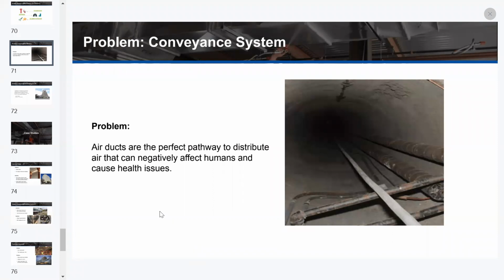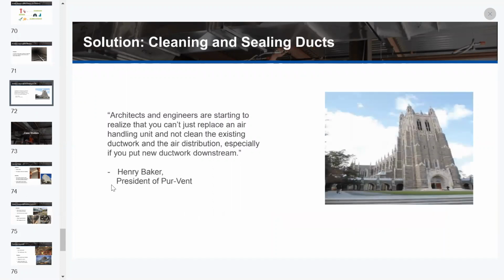Are those refrigerant and gas lines inside a duct? We have seen that. Specifically in the Northeast, where you have low-income housing and you have an exhaust shaft that's great for cable, refrigerant, all kinds of stuff. It's a nice pathway from the top of the building to the bottom of the building. So just cleaning and sealing ducts, right? The solution, making sure that if it's an existing system, that you clean it prior to sealing that. If it's a new construction, if you didn't have duct wrap on the ends of that, trying to protect it during the construction phase, cleaning that as well, making sure that it's sealed as well as you can.